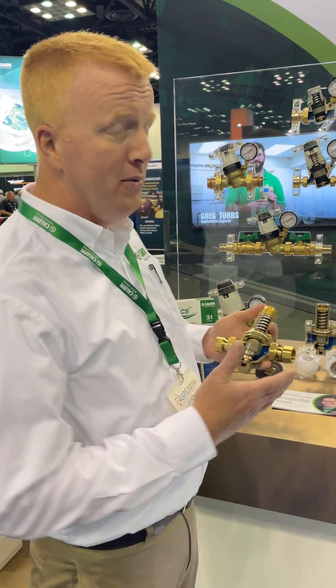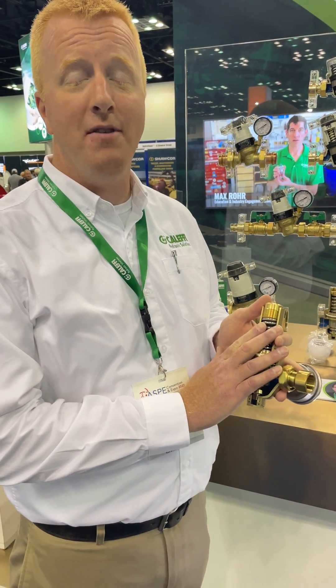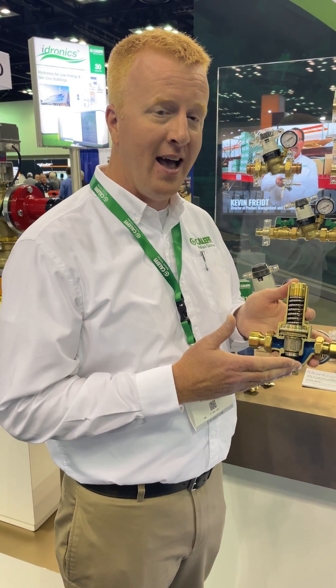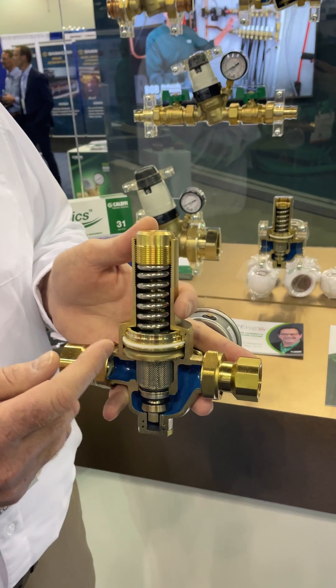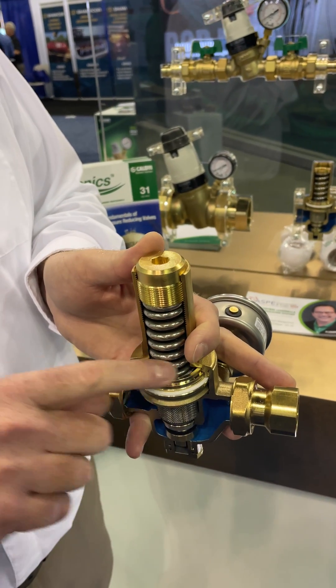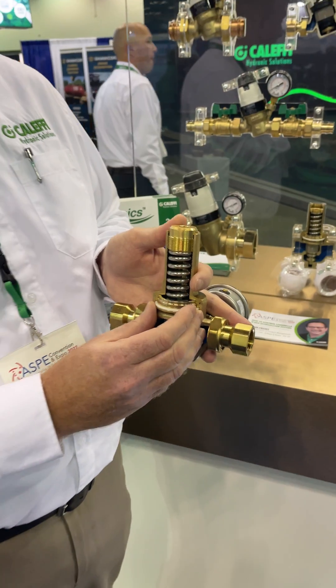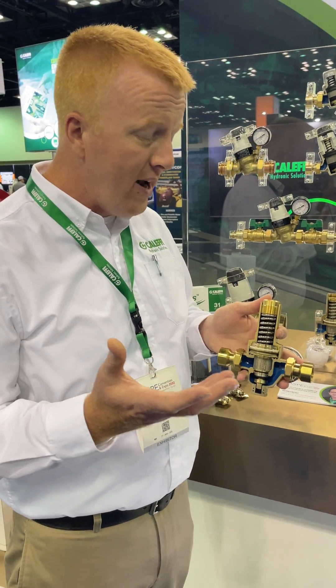We're here at the Caleffi booth. I'm one of the product managers here at Caleffi, and I want to talk about one of the new products we have — the 536 series pressure reducing valve. What's unique about this is that it's a true piston style pressure reducing valve. It does not have an actual diaphragm; it's all metal construction, which makes it a very rugged type of pressure reducing valve. It's going to handle a lot of abuse from, say, water hammer.